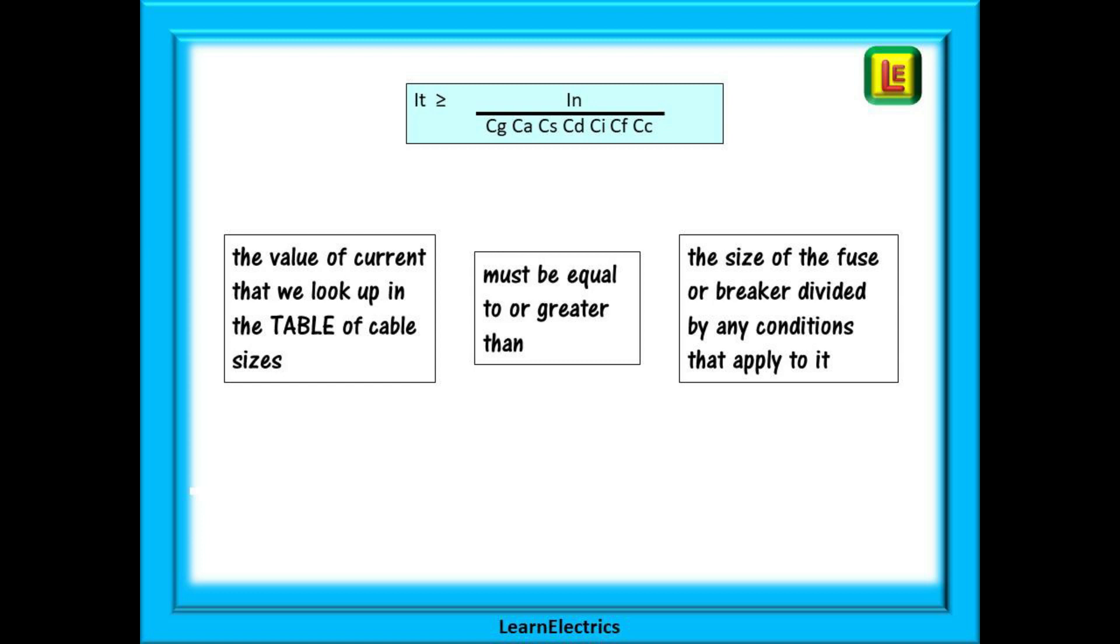It is the tabulated size and will tell us how big is big enough for the full load current. That funny mathematical symbol tells us that the tabulated size must be equal to or greater than the number that we work out with the formula on the right. And this number will be the size of the fuse or breaker called IN divided by all the rating factors or conditions that apply to it.